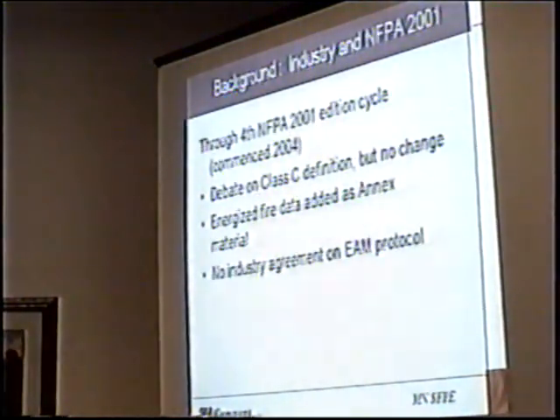No standards. In NFPA 2001, through the 4th NFPA 2001 cycle that commenced in 2004, we've debated the Class C definition. We've had no change. We have a definition now. The definition basically comes out of NFPA 10: a fire that involves electrical equipment where the electrical non-conductivity of the media is of importance. Absolutely nothing to do with fire. It has to do with its conductivity. So it's a lousy definition. That's why I'm saying we don't have a definition of Class C. Let's just call it energy augmented combustion.